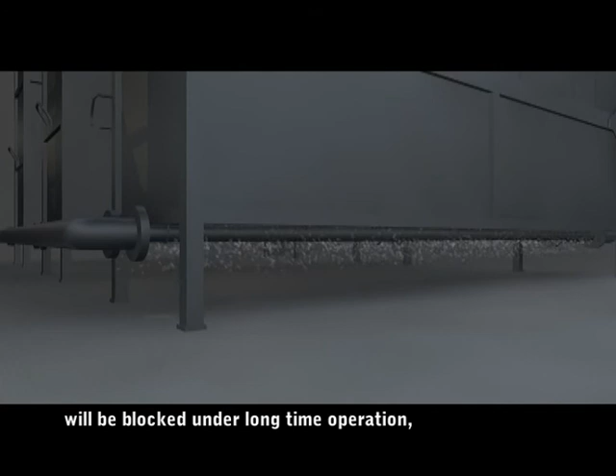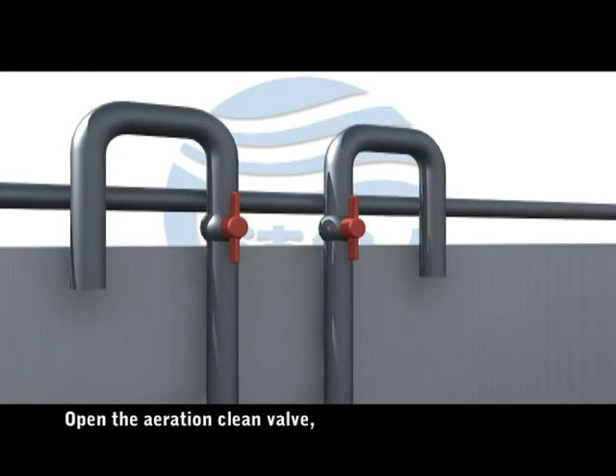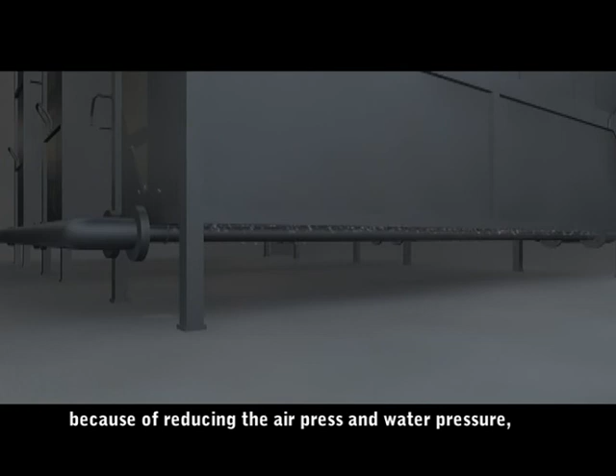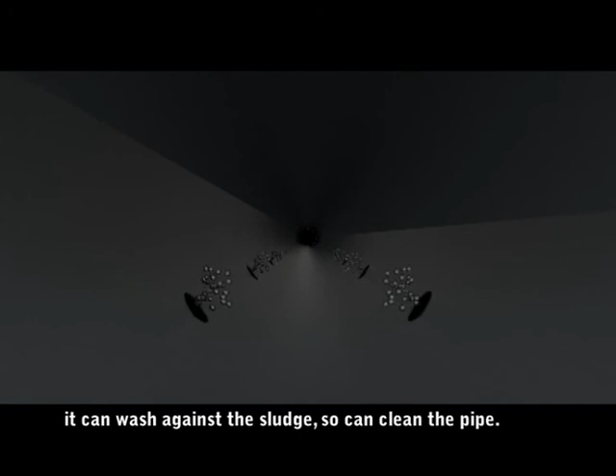Aeration pipe holes will be blocked under long time operation, so we should clean the holes first. Open the aeration clean valves. Because of reducing the air pressure and water pressure, the mix of air and water makes turbulence. It can wash against the sludge, so it can clean the pipe. After cleaning, close the clean valve and return to normal operation.